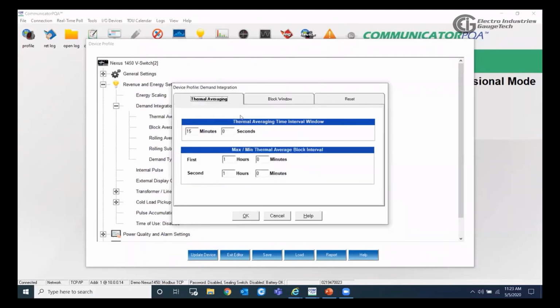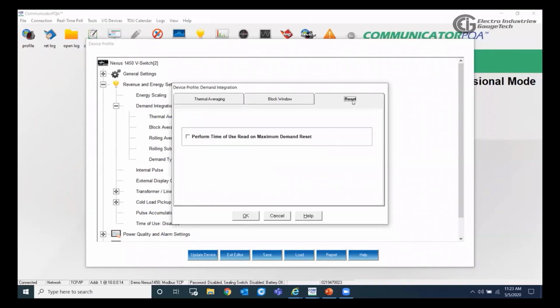We have also the thermal average, where we can set the interval window for the thermal average, and how long would be the max and the minimum thermal average block interval also. We have the option to reset, so we can perform a time of use read on the maximum demand reset. We can enable it from here.